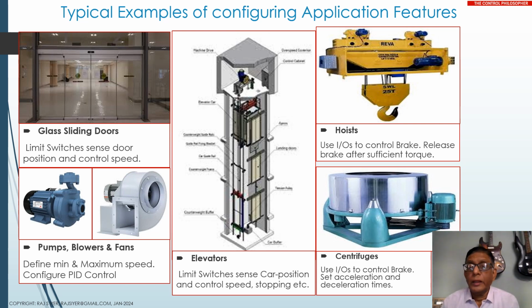Okay. Now, for centrifuges, these are very large inertia things. These are found in pharmaceutical plants. So you have to control the acceleration and deceleration times, which again depends on load and other things. They take a long time to stop, and therefore you have to apply braking, or you can control them through dynamic braking, through a resistor. You can even use regenerative braking. These are the features where mechanical design is simplified by means of the features that are available with VFDs.